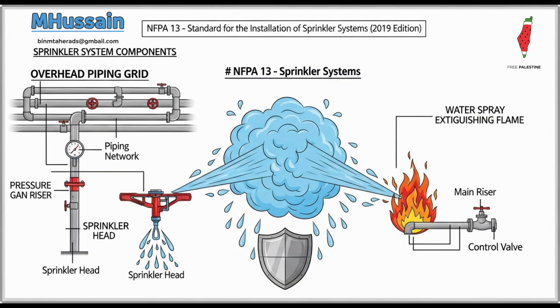And corrosion is obviously a much greater concern in that marine environment, particularly with constant saltwater exposure. Absolutely. The standard specifically mandates that sprinklers shall not be rendered ineffective by corrosion related to saltwater entrapment, especially within the return bend or sprig of the pipe connecting to the sprinkler head. This forces really careful design practices to prevent the pocketing of corrosive salt materials that could quickly destroy a vital component like the sprinkler itself.